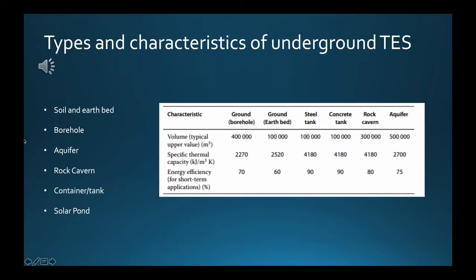Soil and earth bed TES: heat or cold can be transferred into underground soil for storage and subsequent recovery. Soil and earth bed TES systems are often shallow, for example earth beds. The use of earth as a TES medium is often restricted to new construction, since the application requires installations in the ground beneath the structure, making retrofit work difficult.